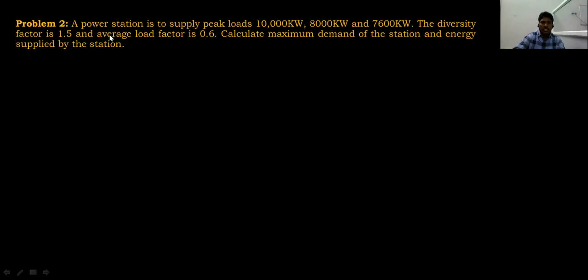The second problem: a power station is to supply peak loads of 10,000 kilowatts, 8,000 kilowatts and 7,600 kilowatts. The diversity factor is 1.5 and the average load factor is 0.6. The load factor and diversity factor are given, along with the individual maximum demands of 10,000, 8,000 and 7,600 kilowatts. The question is to find the maximum demand on the station and the energy supplied by the power station. From the previous video, we know the formula: diversity factor, which is 1.5, is equal to the sum of individual maximum demands divided by the maximum demand on the power station.